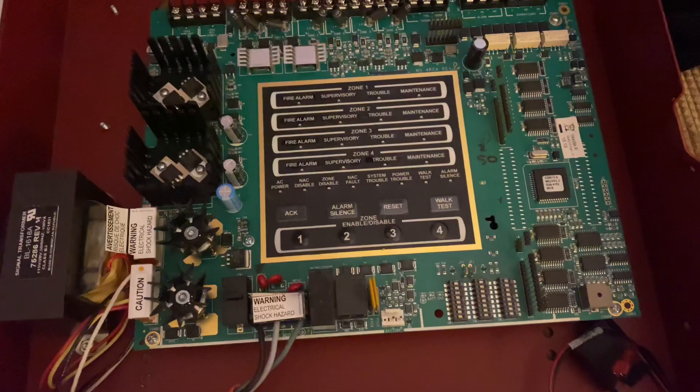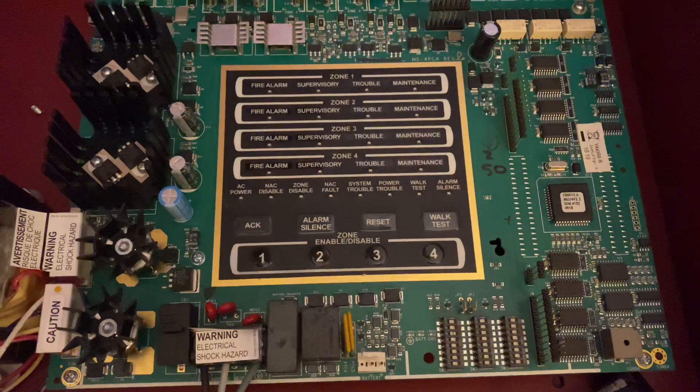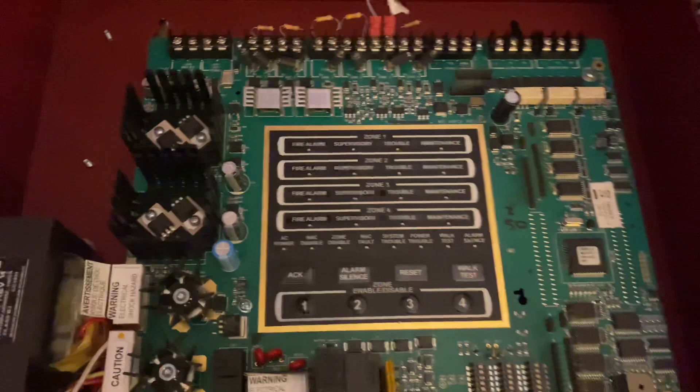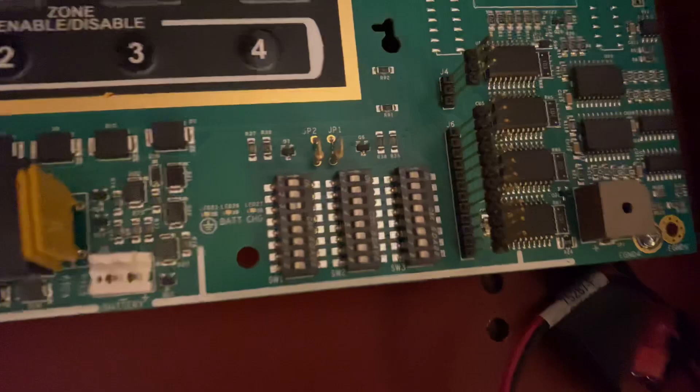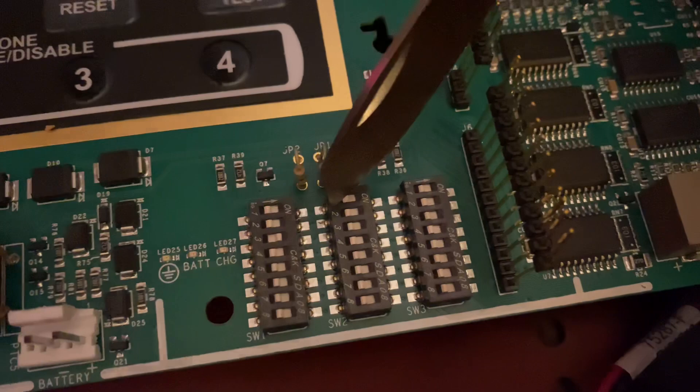Today I'm doing a video about this panel, my Gamewell Flex 404. I'm going through the programming DIP switches. I did this with the MS-4 a while ago, but that video wasn't great. There's a little manual here for the DIP switches, but they don't really detail what they do, so I'm going to explain it. You have three sets of DIP switches: Set 1 is general programming, Set 2 is initiating device circuit programming, and Set 3 is NAC programming.